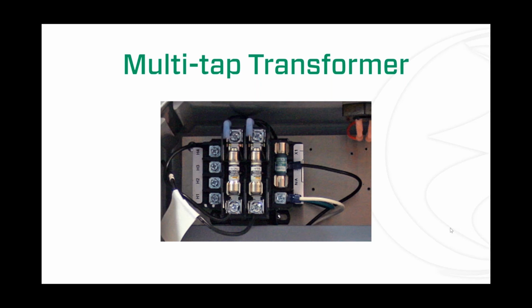Another thing that I want to mention here is the fact that these transformers have fuses. These fuses are very specific fuses that go in these guys, and they are very expensive, maybe $50 a fuse. So again, you want to make sure things are wired right before you turn on the power. Take an extra minute or two and just double check things. Like I said, use your meter, it's your friend. Make sure you know what that incoming voltage is. You want to get this right. You don't want to make a mistake here.